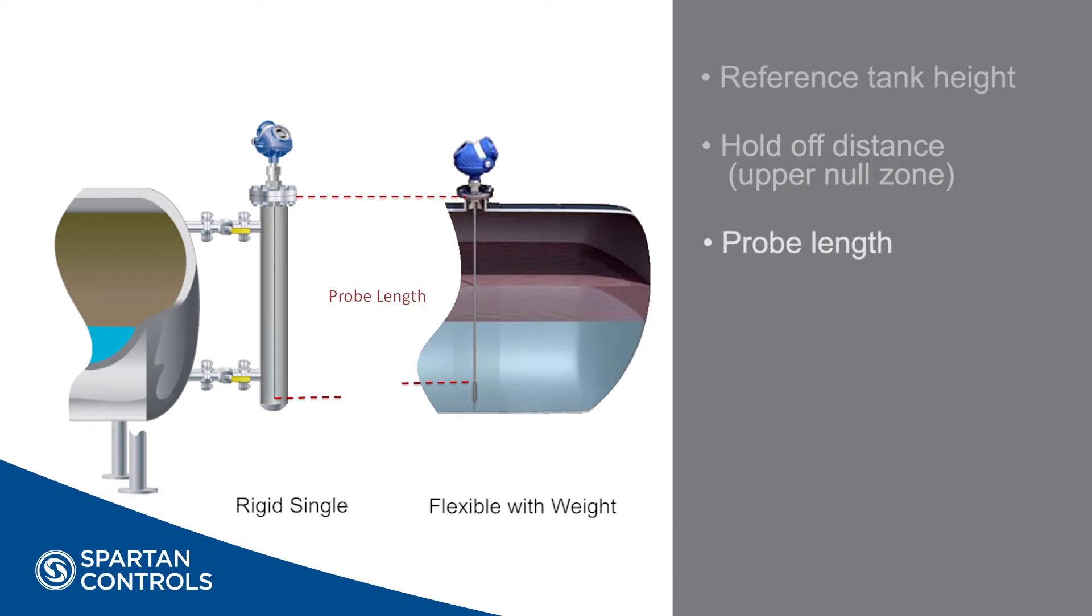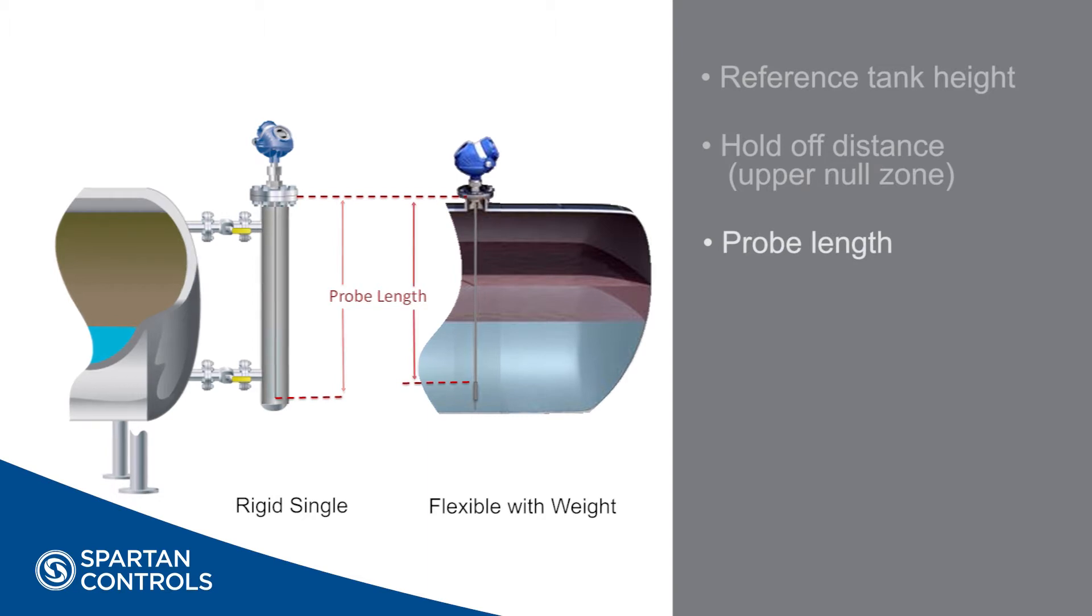Probe length is measured from the factory but should be verified and noted before installation. On a rigid probe, the measurement is made from the bottom of our flange to the tip of the probe. On a flexible probe, the measurement is made from our flange to the top of the weight.